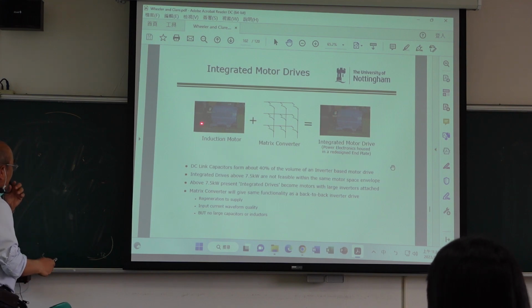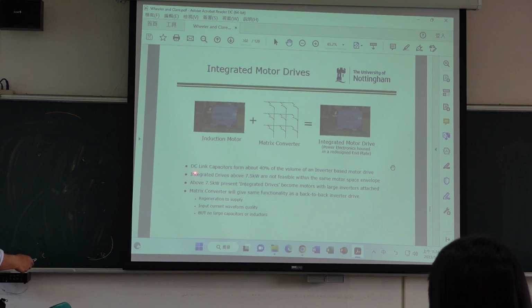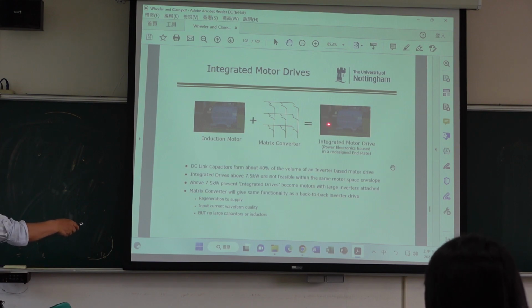So it is only for middle and low power motor drives. Above 7 kilowatt, the integrated drive becomes motors with a large inverter, so you need a large inverter, and then the inverter cannot go here.